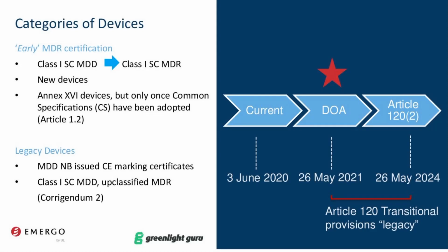And then, of course, the example that most of us probably are familiar with are the software products, which possibly were classified as Class 1 self-certified according to Rule 12 under the MDD, but now because of Rule 11 in the MDR, potentially would be up-classified. And then one last comment about this slide is that there are transitional provisions in Article 120 for these legacy products, and that essentially they can continue to be marketed after the date of application and until 26 May of 2024. So they have this, and that's provided for the MDD notified body issued CE marking products. That's of course provided that the certificates have not expired.